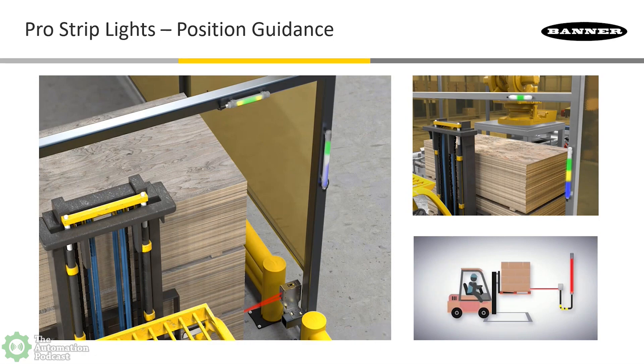For the listeners, this can be fully dynamic. Even with the discrete ones, we take a pulse frequency or pulse-width-modulated input, which can come directly from some of the Banner laser and radar sensors. We take a parallel Y-splitter cable, put the light on one side, the sensor on the other, power coming into the third leg — and this can be a system completely independent of anything else going on on the equipment. Totally plug and play — just stick it on whenever you like, or still pull off that sensor information and push it back to the control system if needed.